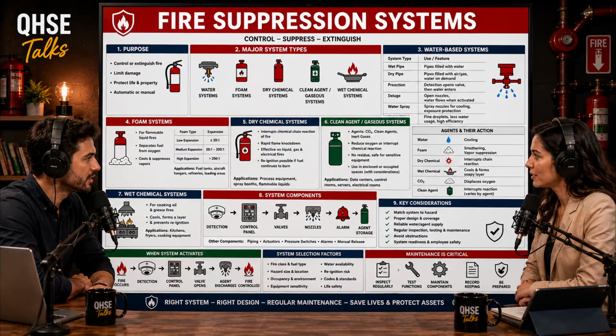What does that actually look like for a fire system? A huge part of this is looking for subtle creeping degradation. For example, the engineering manuals discuss a pervasive phenomenon called loading. What exactly is loading? Loading is the slow accumulation of foreign materials directly onto the sprinkler heads. Think about a woodworking shop generating fine sawdust, or an auto body shop where overspray from paint slowly drifts up to the ceiling. Oh, wow. The sprinkler head just gets coated in a layer of grime.